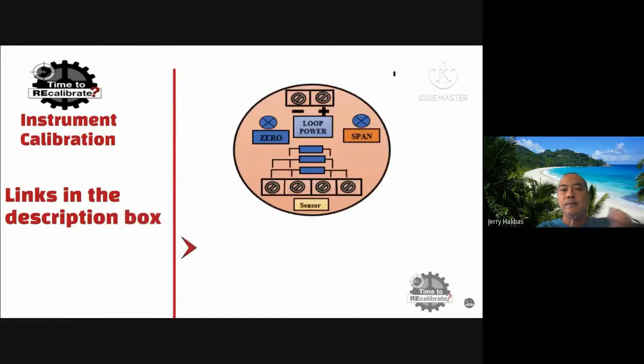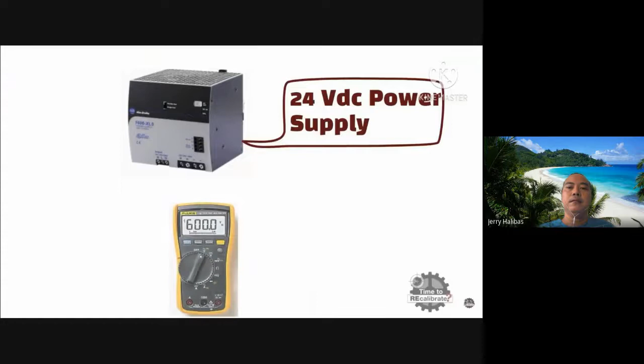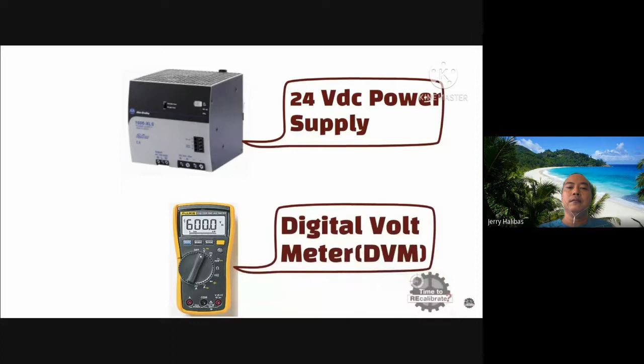In this video, I am going to show the calibration procedure of temperature transmitter. First of all, what do we need in calibration kit? Firstly, we need thermocouple or RTD simulator. Secondly, we need 24-volt DC power supply. Lastly, we need digital voltmeter to measure 4 to 20 mA output of transmitter. Let's learn how to perform calibration of temperature transmitter.